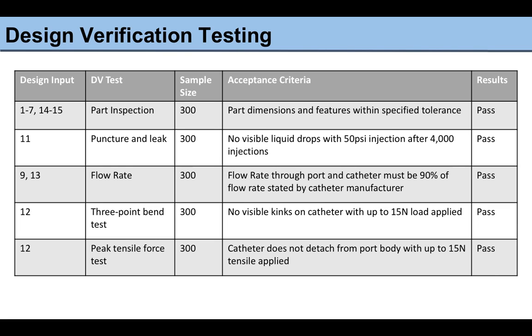was qualifying. The first test was part inspection, where the acceptance criteria was part dimensions and features are within the specified tolerance on the drawings of the parts, and this test passed. Our second test was our puncture and leak test to make sure that our device would not leak and could be punctured many times, and the acceptance criteria for this was no visible liquid drops with 50 psi injections after 4,000 injections, and this test passed.